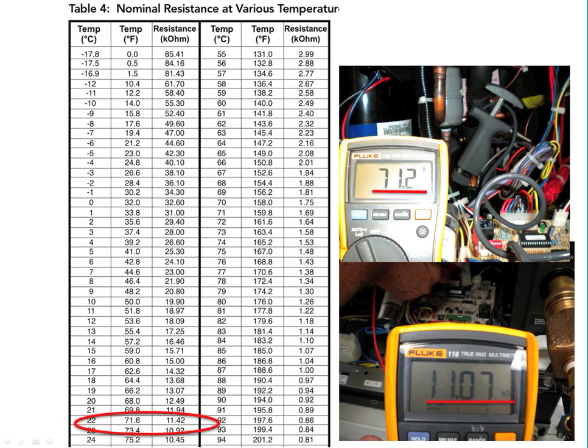Well, again, in that same vicinity, as I just mentioned, that menu for the fault codes, back in the CXM IOM section, Installation, Operation, and Maintenance, you're going to find a thermal resistance, ohm resistance chart. In other words, you can convert from ohm resistance to temperature. So you're going to see here, near the bottom of your screen, we circled the 10.92 and the 11.42 ohms resistance, because we're kind of in between those two with our 11.07. And again, if you look at that chart over on the left-hand side in the temperature column, somewhere around 71.6 to 73.4 is the general vicinity of that temperature. And if you look on the right-hand side of our picture, we had a 71.2 degree reading. And I will tell you, for a thermistor, that's plenty accurate enough. That shows that it's right in the range it needs to be.